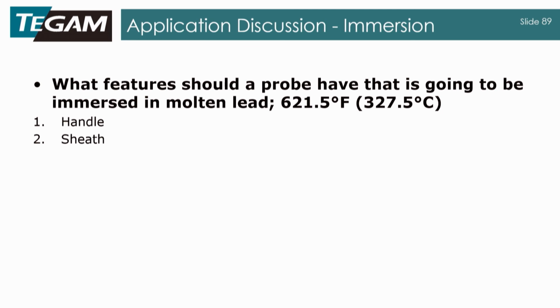For the sheath, stainless steel should work fine. As we saw, 900 degrees C was the top end for stainless steel. 327 is well within that. For the junction, ungrounded is going to be the best for molten metals, and that's because molten metals are conductive, and as we said, if you had a grounded sheath, you could introduce electrical interference and problems with that. So ungrounded is going to be the best here because you're going to be insulated from the molten metal that you're measuring.